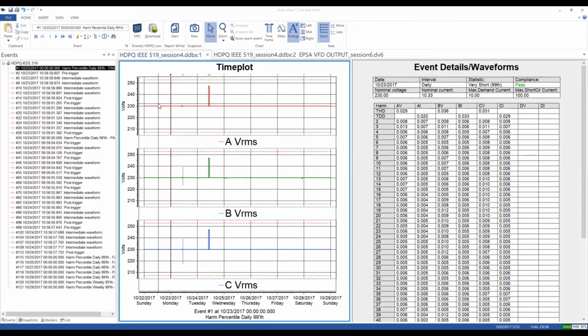And that means you can plot any parameter, do anything you normally do, but what DranView will show you is exactly what is in the instrument, which you can see in the instrument as well: each of the reports produced. That is 2 weekly reports, or actually 3 weekly reports, and a daily report for very short time harmonics. And you can see one highlighted here in the event list.